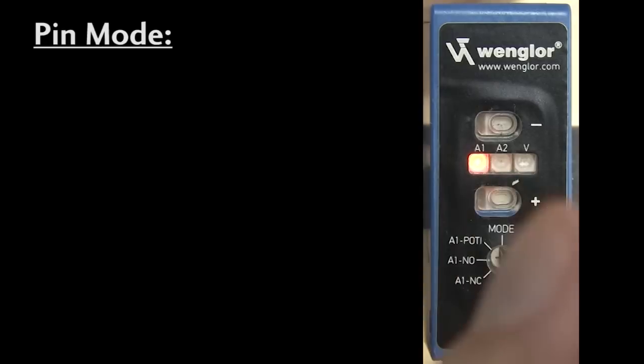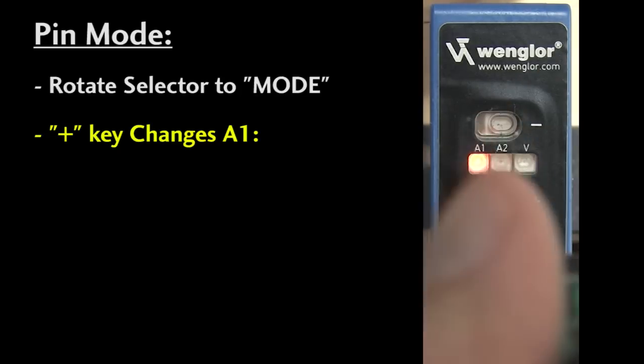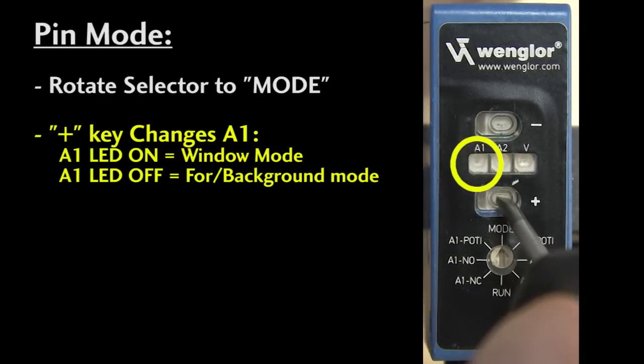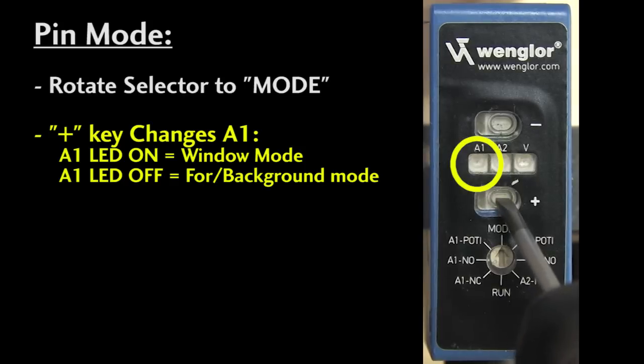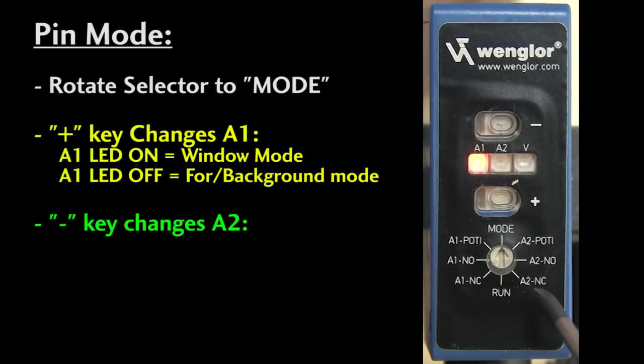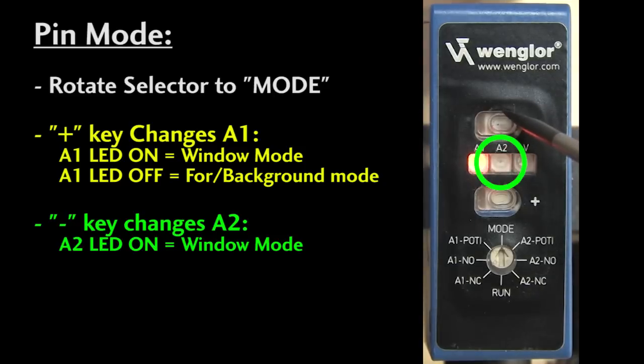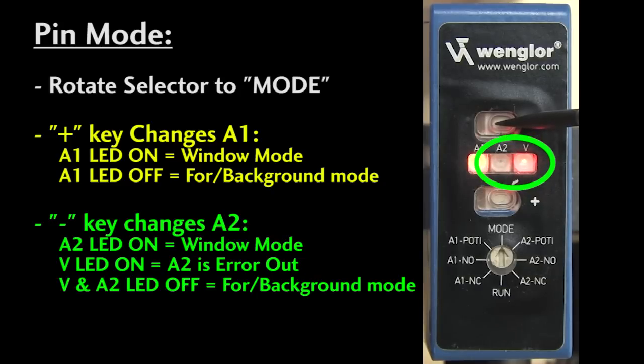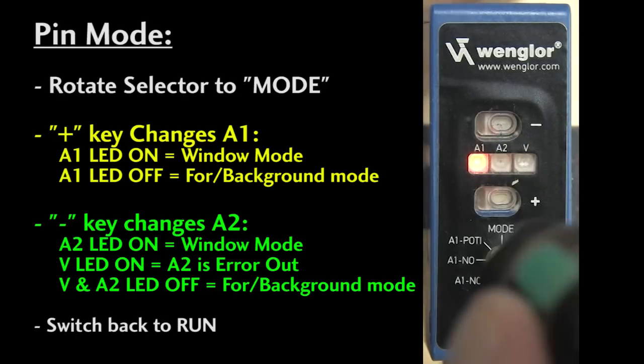Let's try it. Rotate the selector to mode. The plus key changes A1 between window mode – the LED on – and foreground background mode – the LED off. Let's put A1 in window mode. The minus key changes A2. If A2 is lit, it's in window mode. If the red V is lit, that means that A2 is an error out signal. And if both V and A2 are off, A2 is the default foreground background mode. We'll leave A2 there as a foreground background detection. Switch back to run and you've set the mode.